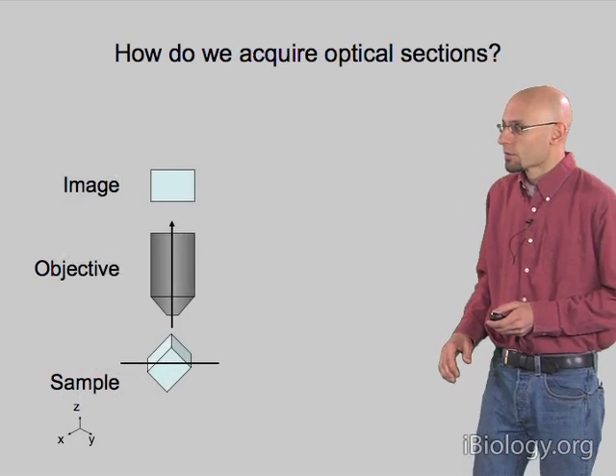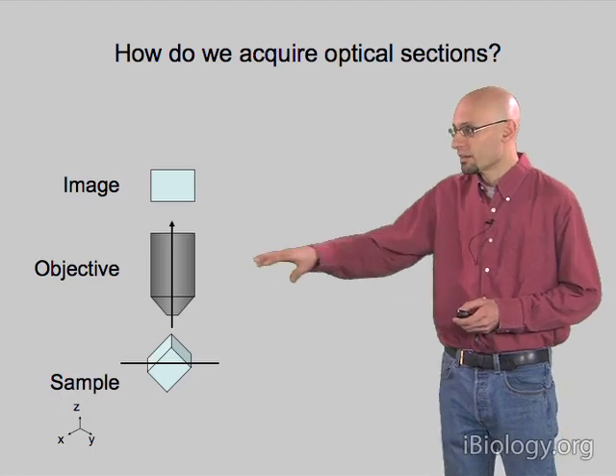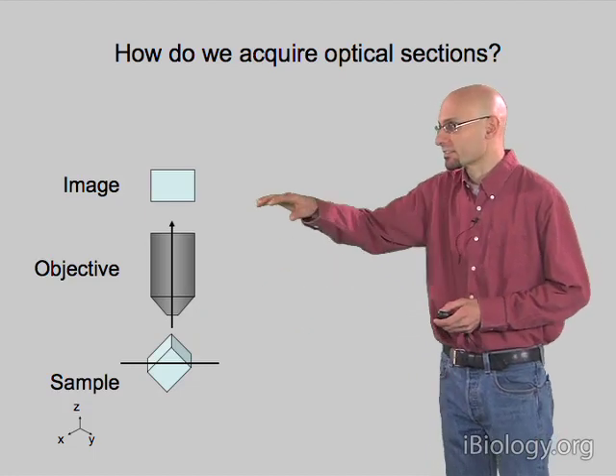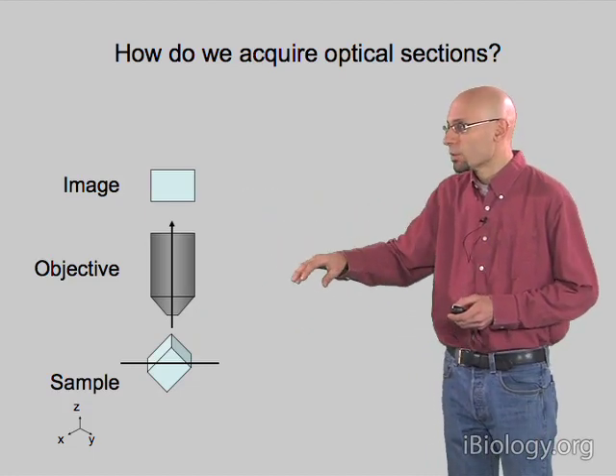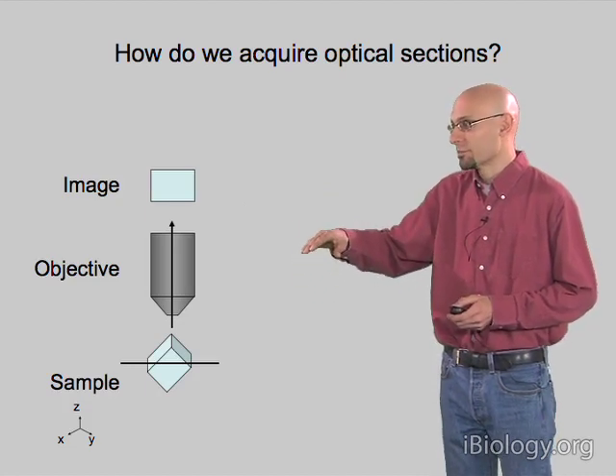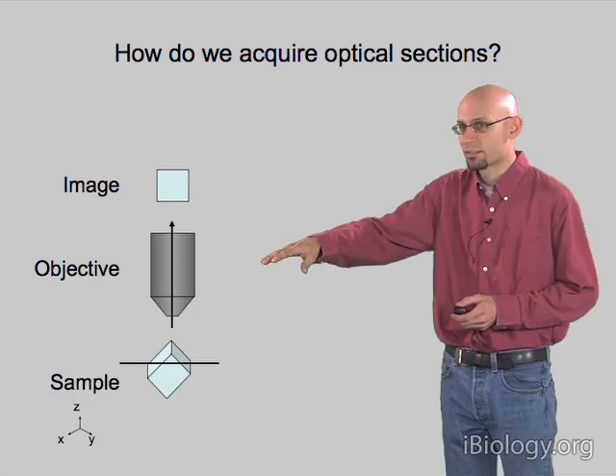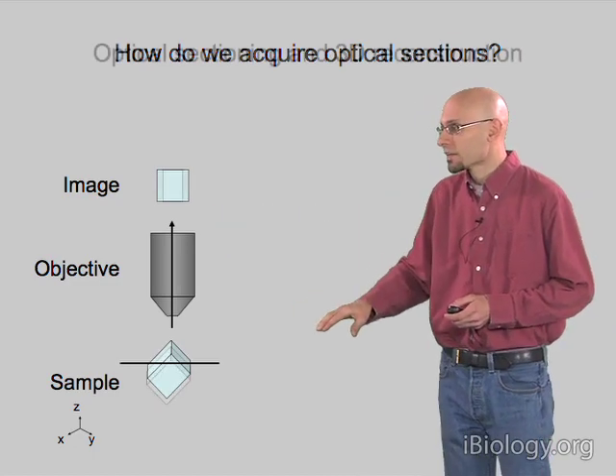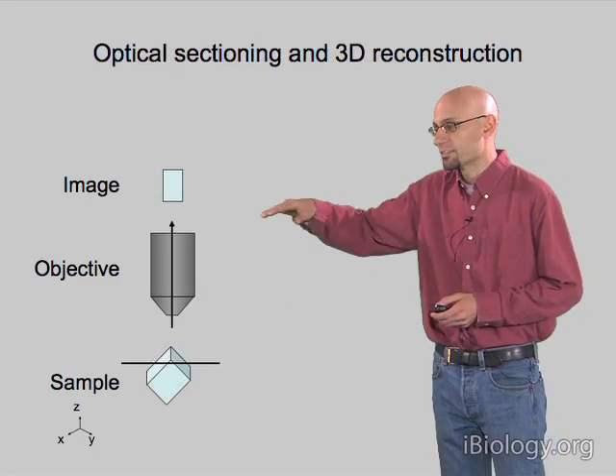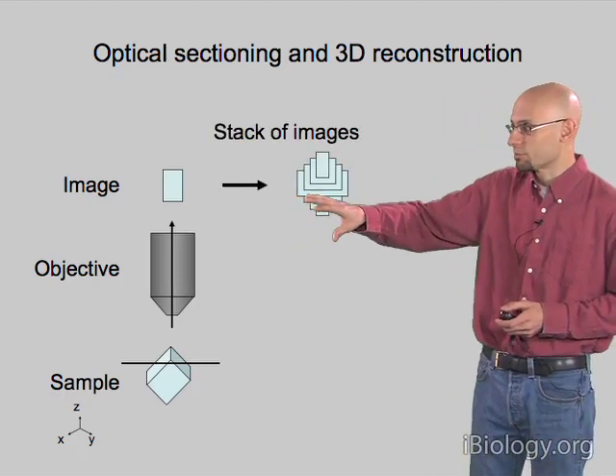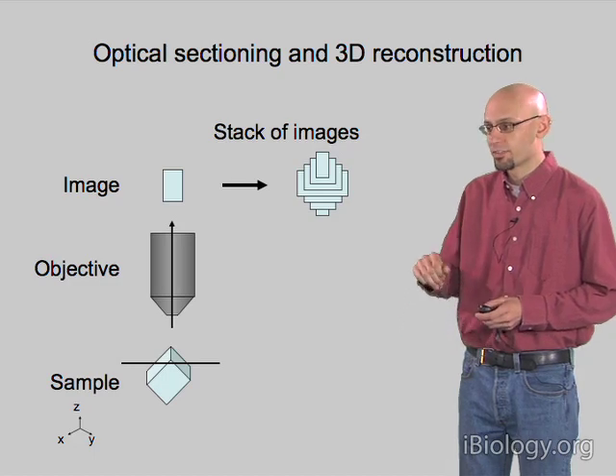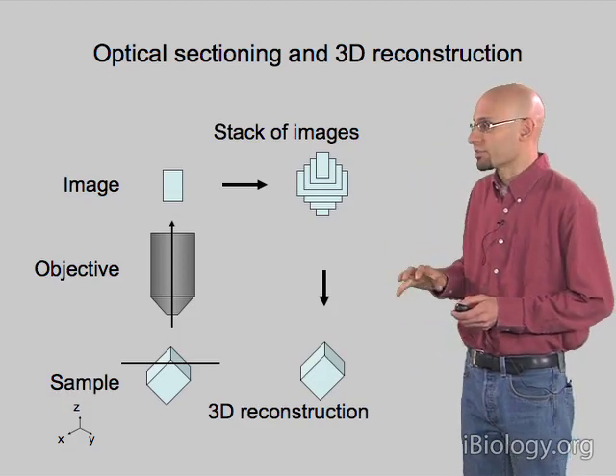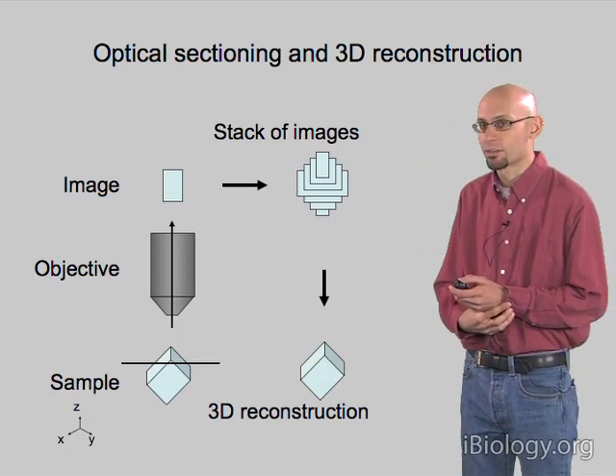We need a microscope where we can take images at different heights. We have our sample here, illustrated by this little cube. We take a picture of it, so we get a slice through the sample. We then step the focus — we physically move the sample up or down — to get a second slice through a different portion. We can keep doing this, getting slices through different parts of the object, and then get a stack of images which we can assemble into a three-dimensional structure in the computer.